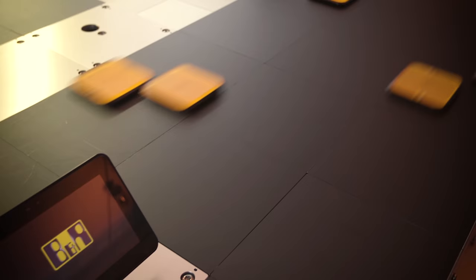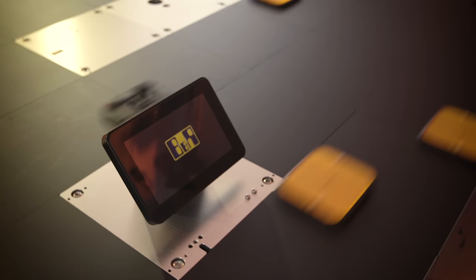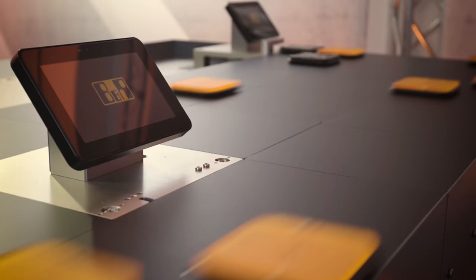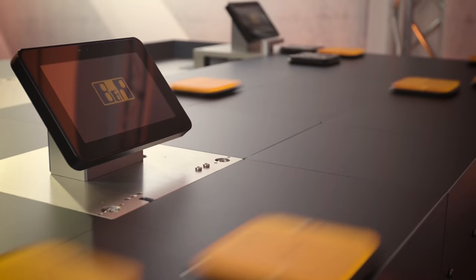ACOPOS 6D is a product transport system based on magnetic levitation. ACOPOS 6D's permanent magnets in the shuttle interact with the magnetic field generated by the motor segments. The resulting force makes the shuttle float in the air. Because of this, ACOPOS 6D doesn't need a guide system. The shuttles don't follow a predefined path. They can perform any kind of movement on the surface of the motor segments, giving machines and lines unlimited movement flexibility in two dimensions.